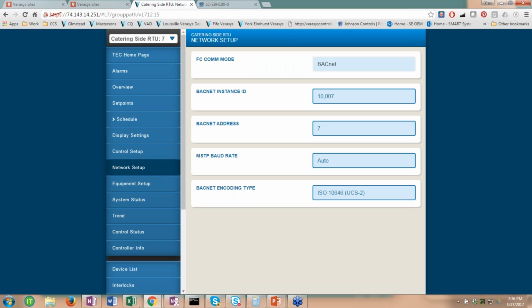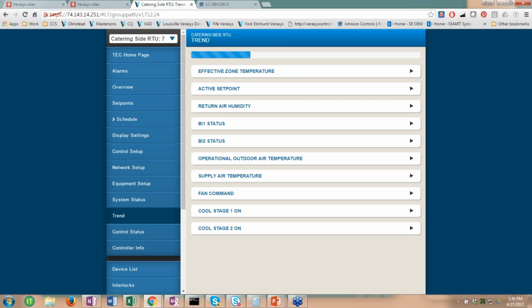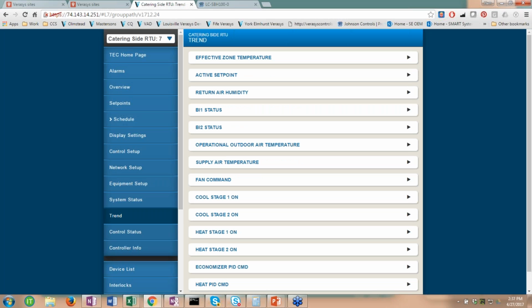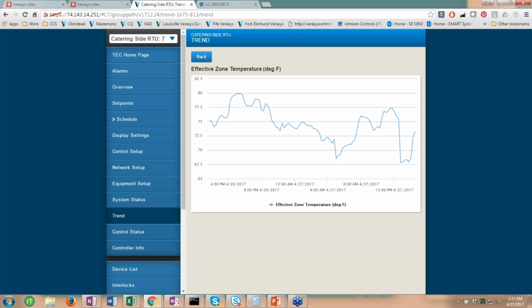And then you've got your network setup. And one of the network setups you could do here, you could actually physically change the address, which I'm going to try to show you guys in a minute. One of the other nice features here, and again, I'm going through the Smart Building Hub, is what's called trend. These trends are all predefined within the system, within the controller. It's not in the Smart Building Hub. It's all in the controller.